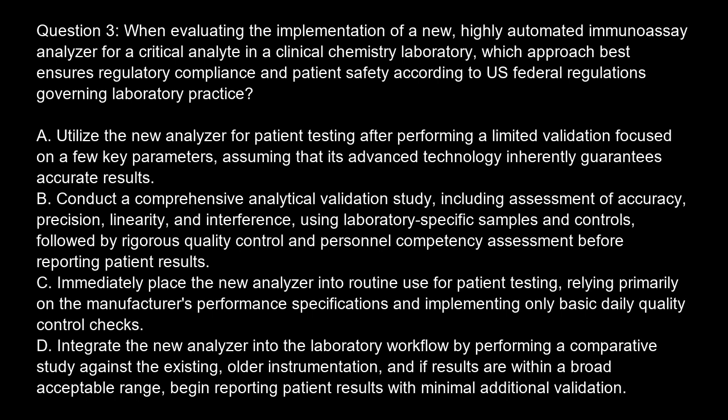Option C. Immediately place the new analyzer into routine use for patient testing, relying primarily on the manufacturer's performance specifications and implementing only basic daily quality control checks. Option D. Integrate the new analyzer into the laboratory workflow by performing a comparative study against the existing, older instrumentation, and if results are within a broad acceptable range, begin reporting patient results with minimal additional validation.